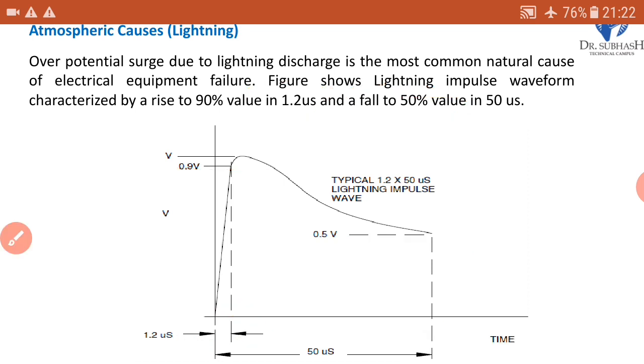Overvoltage surge due to lightning discharge is the most common natural cause of electrical equipment failure. This is most common because in the rainy season we frequently see lightning strikes. Here we have given one example. The figure shows a lightning impulse wave characterized by a rise to 90% of its value in 1.2 microseconds, and a fall to 50% value in 50 microseconds. So this is a typical lightning impulse wave, and it is frequently seen in the rainy season. So the natural effect is generally due to lightning.